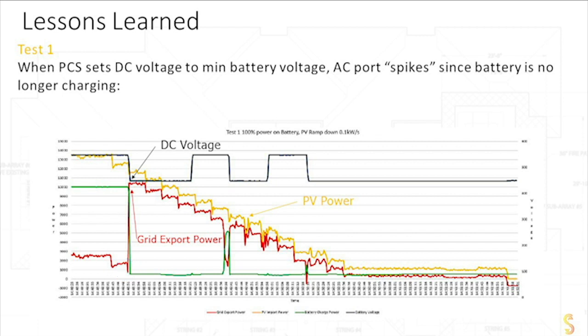So the battery is off now because the voltage has been set below. All the solar is now going out into the grid, and the difference now between the yellow line and the red line is just inverter efficiency, basically, and system efficiency. So that's why the red line and the yellow line are slightly off from each other. One is DC and the other is AC, so to speak.